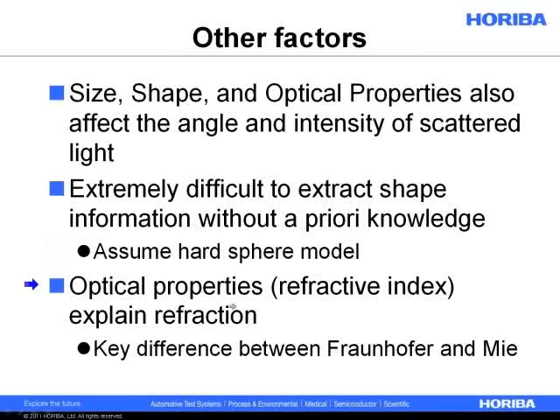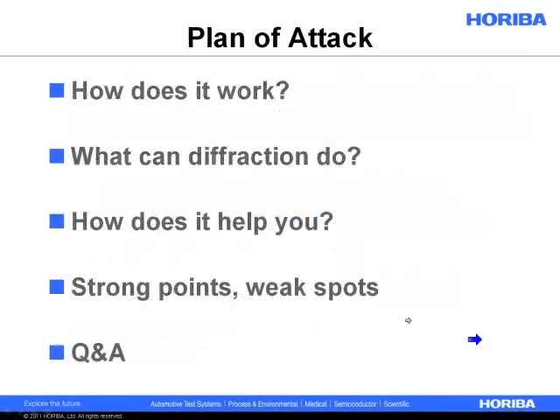Optical properties basically means refractive index, and it helps explain refraction. This is also the key difference between the Fraunhofer approximation and the Mie scattering theory — this is why Fraunhofer runs out of steam around 20 microns, and Mie can be carried through into the nanometer range. At the end of the presentation, I'll have several previously recorded webinar references if you'd like to learn more about diffraction theory.